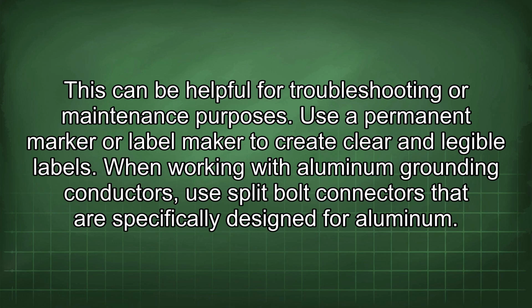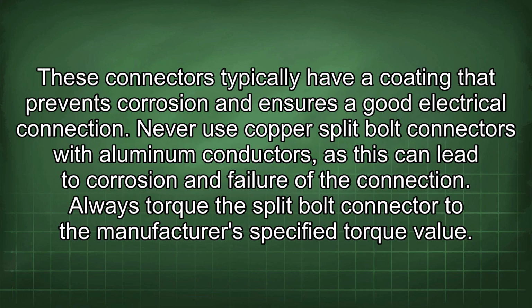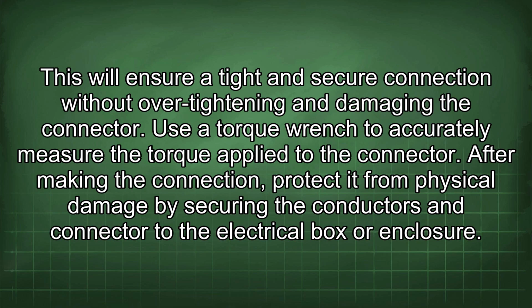When working with aluminum grounding conductors, use split bolt connectors that are specifically designed for aluminum. These connectors typically have a coating that prevents corrosion and ensures a good electrical connection. Never use copper split bolt connectors with aluminum conductors, as this can lead to corrosion and failure of the connection. Always torque the split bolt connector to the manufacturer's specified torque value. This will ensure a tight and secure connection without over-tightening and damaging the connector. Use a torque wrench to accurately measure the torque applied to the connector.